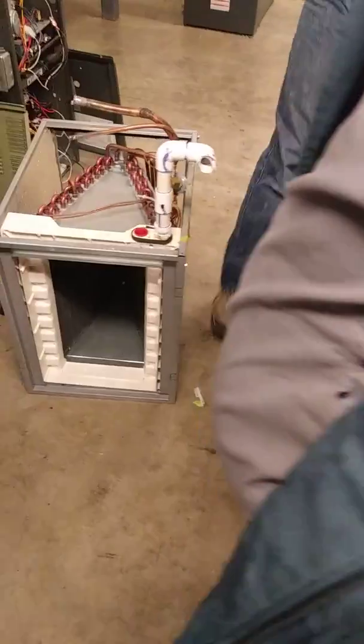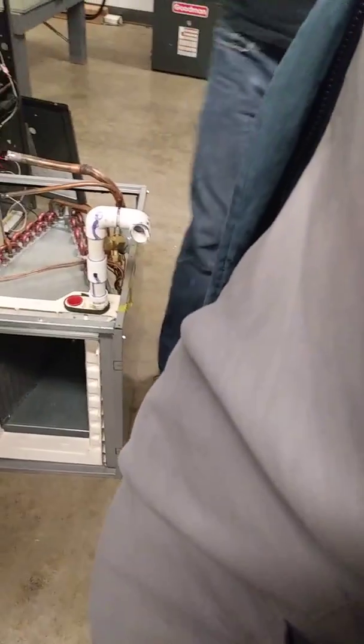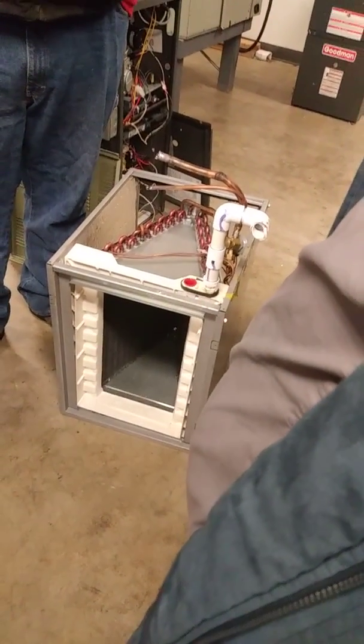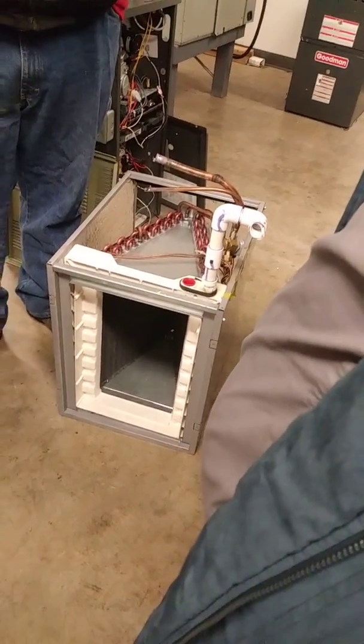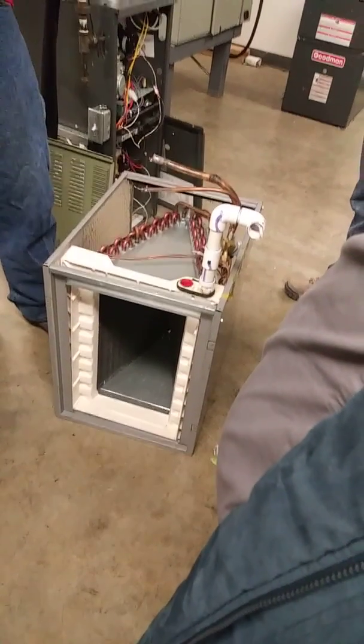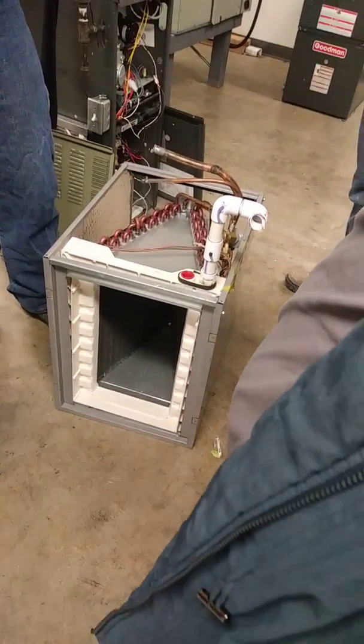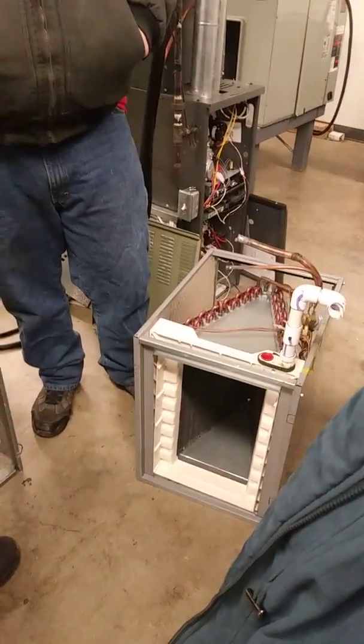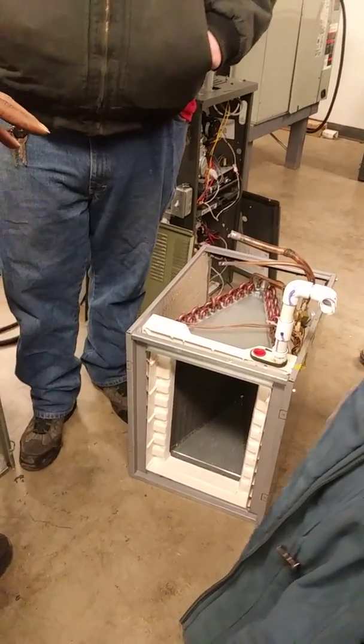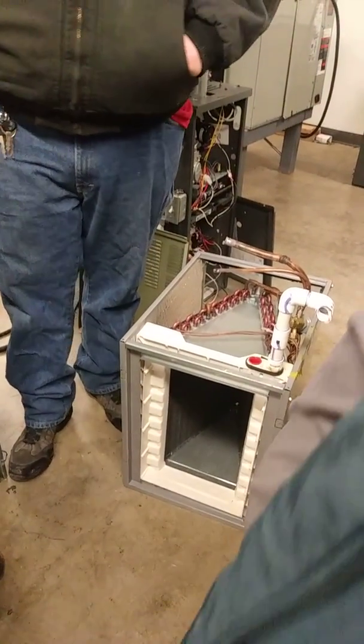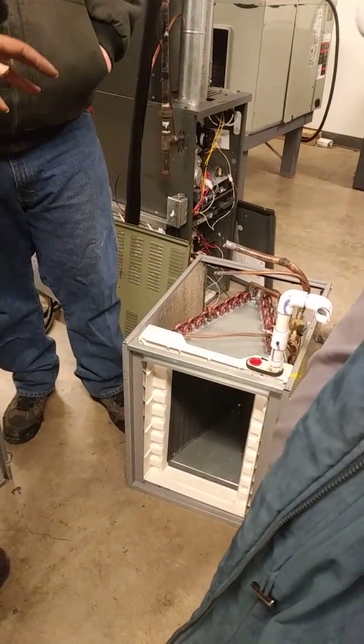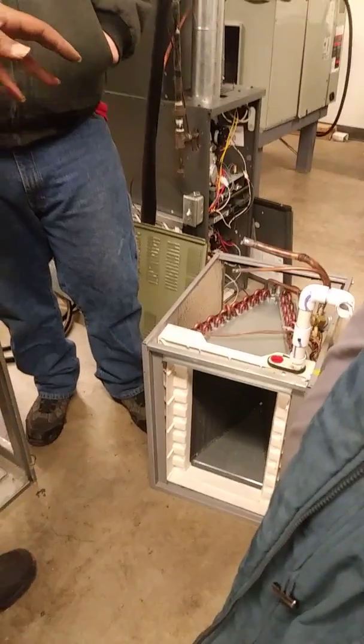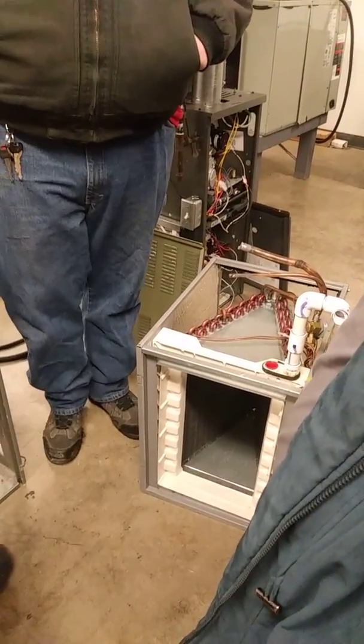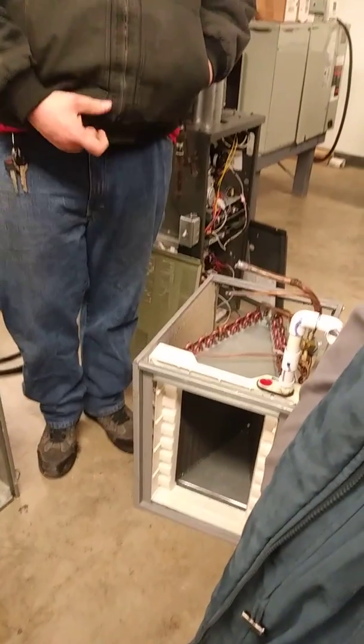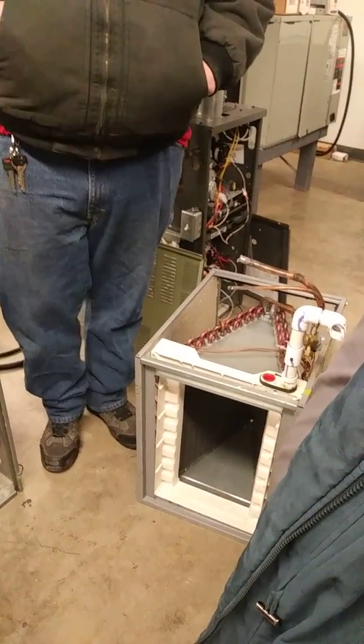So if that turns out to be an issue, we could use the duster on it, right? No, you can't use dust on that. It's like carpet, literally. Because you have oils and stuff from the A coil sweating in the summertime, the dust gets up in there and it's caked on. You need coil cleaner. It's the same type of cleaner that's used for the outdoor condensing units. Some of them do both. They call it a condensing evaporator cleaner, and they do have some that you spray on and you don't need any water. But it'll be kind of hard, like I said, in the house. You just never know what you're dealing with.